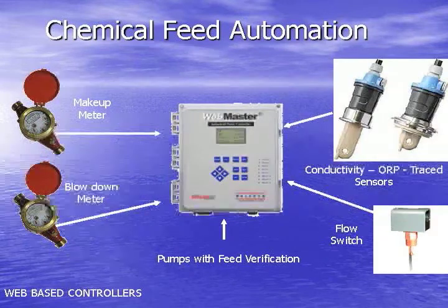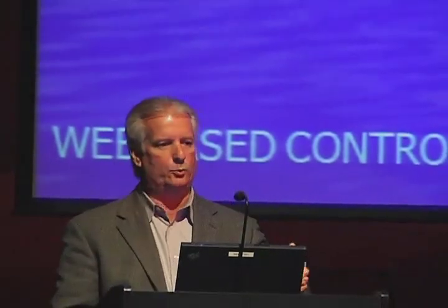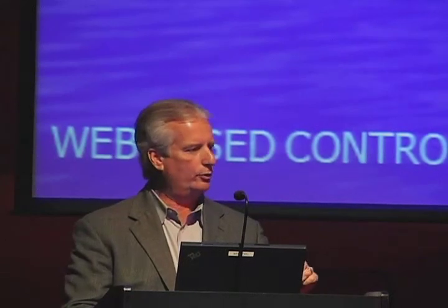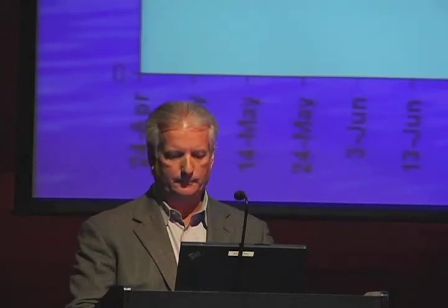And that's important because as you push the cycles and as you push the chemistry, you need to make sure you have good automation. So I would encourage each of you to look in that, and also it can take water meter signals and actually calculate how much water you use per day and everything else. And that would be different from the program that they're talking about earlier. But I would encourage you to look at some of the controllers. They're very good, they're very effective, and they're fairly accurate.